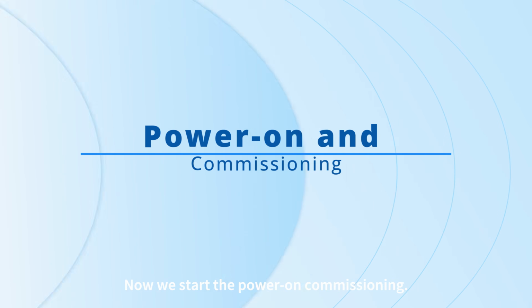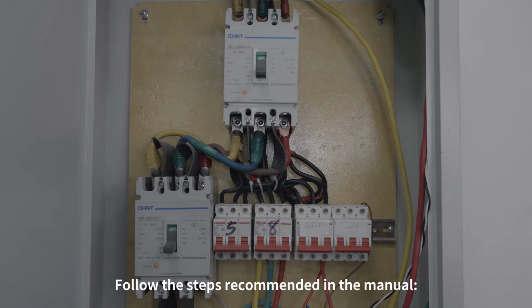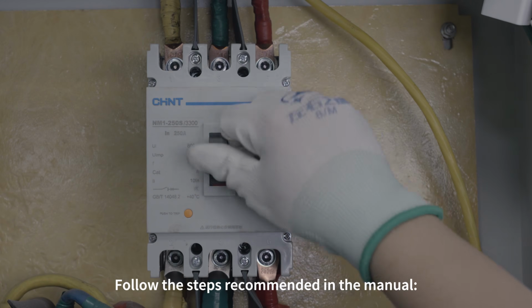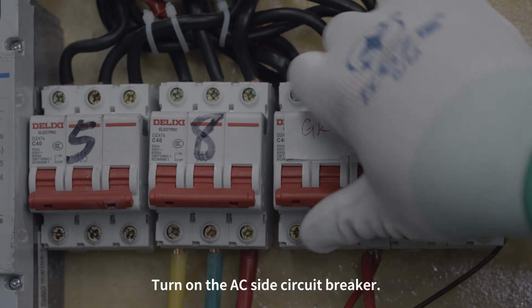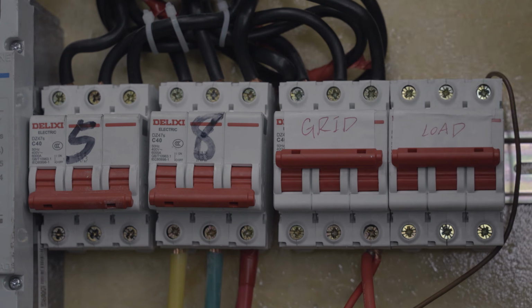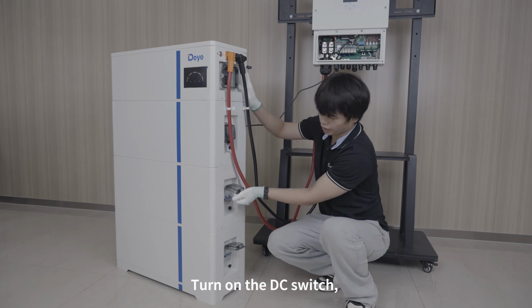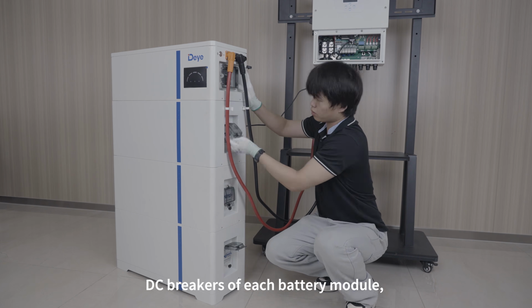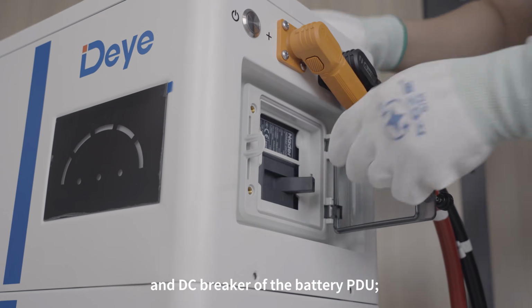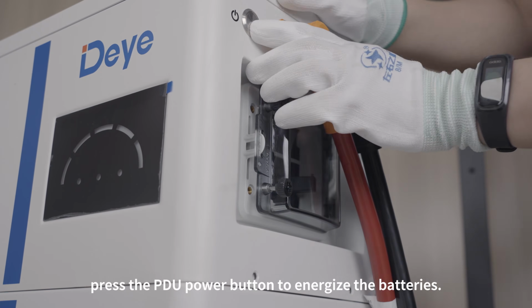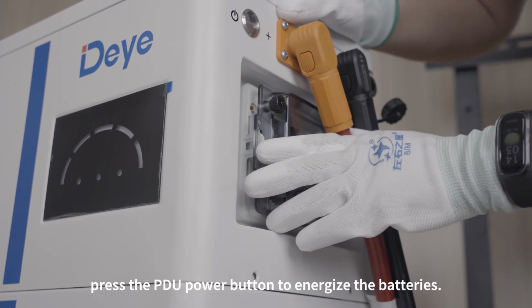Now we start the power on commissioning. Follow the steps recommended in the manual. Turn on the AC side circuit breaker. Turn on the DC switch, DC breakers of each battery module, and DC breaker of the battery PDU. Press the PDU power button to energize the batteries.